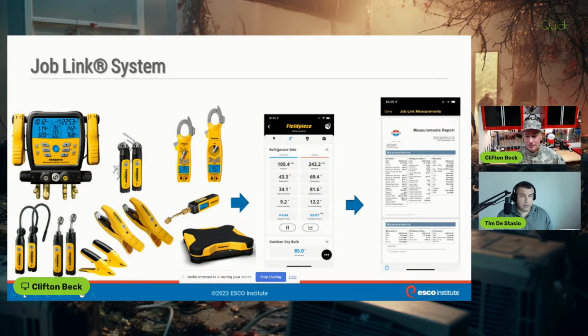There is not that much of a learning curve anymore to learn MeasureQuick with their guided workflows. It literally takes me 15 minutes to do a performance check on the system. The guided workflows walk us right through the whole process. And so we have to pay attention to those things, even paying attention to some of the smaller points of performance, like approach temperature. That's the difference between liquid line temperature in heating mode and the return air temperature coming in. And you can very quickly screen a unit whether it has a charge problem or an airflow problem just by checking that temperature difference. If it's too low or too high, and I've put out several videos on how to screen that. Good videos.